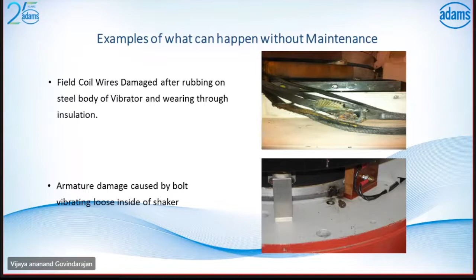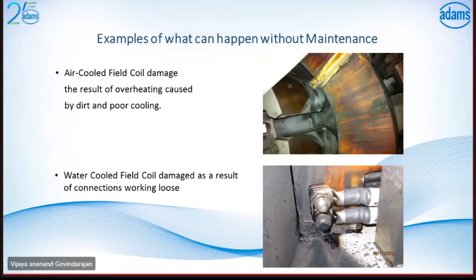As I said, these field coils generate excessive heat due to the heating effect and due to handling of excessive current. So this is damage as a result of overheating and poor cooling. Generally, when these high current carrying coils generate excessive heat, this heat needs to be compensated by a proper cooling system. We provide you a proper cooling system, but over a period of time, we need to maintain this cooling system. Without maintaining it, this kind of damage can happen. On a frequent basis, we need to check the tightness of the field coils. That will be checked in our preventive maintenance.